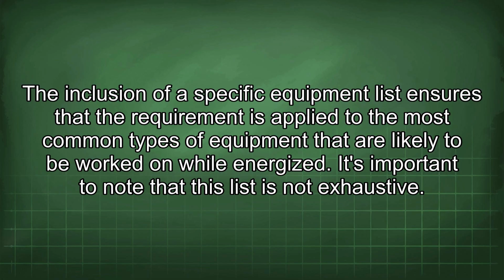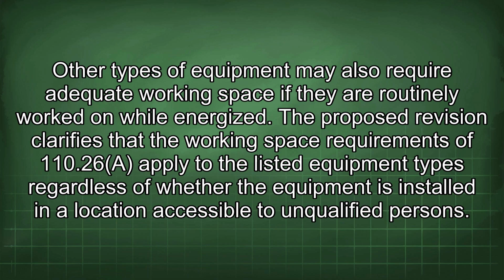The inclusion of a specific equipment list ensures that the requirement is applied to the most common types of equipment that are likely to be worked on while energized. It's important to note that this list is not exhaustive. Other types of equipment may also require adequate working space if they are routinely worked on while energized.